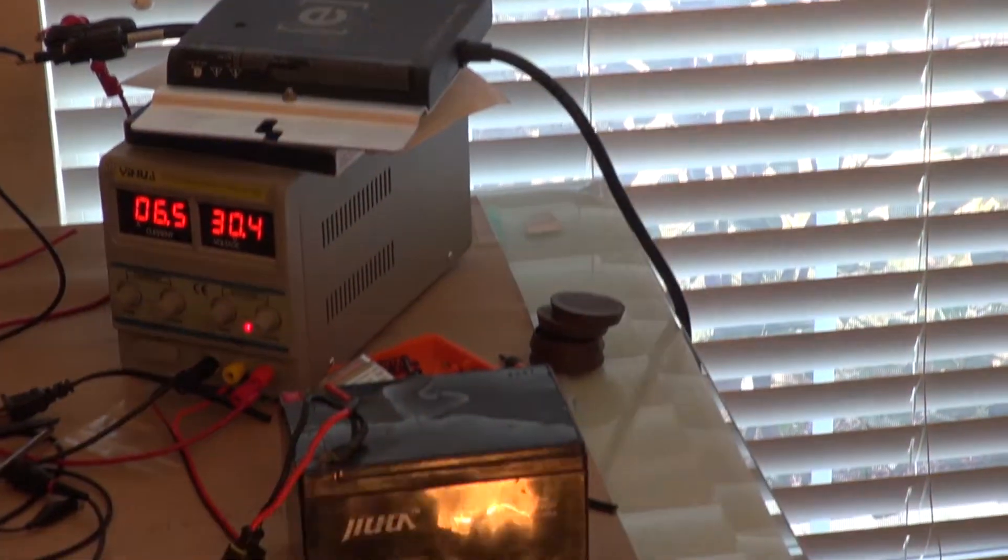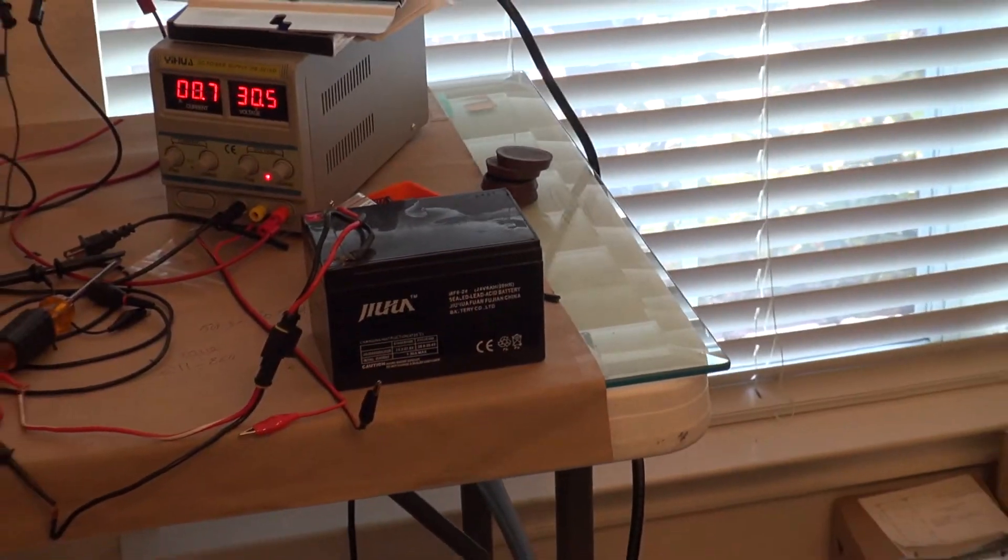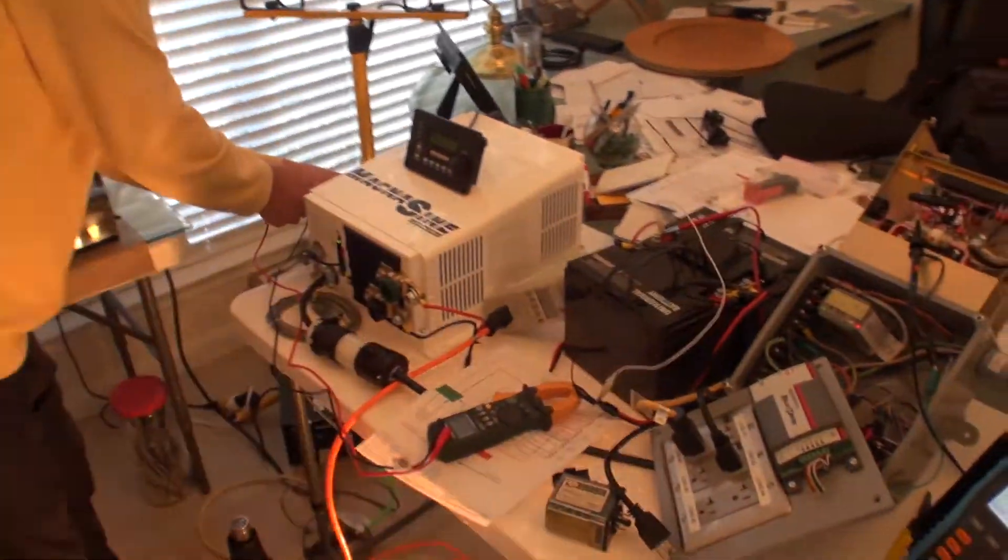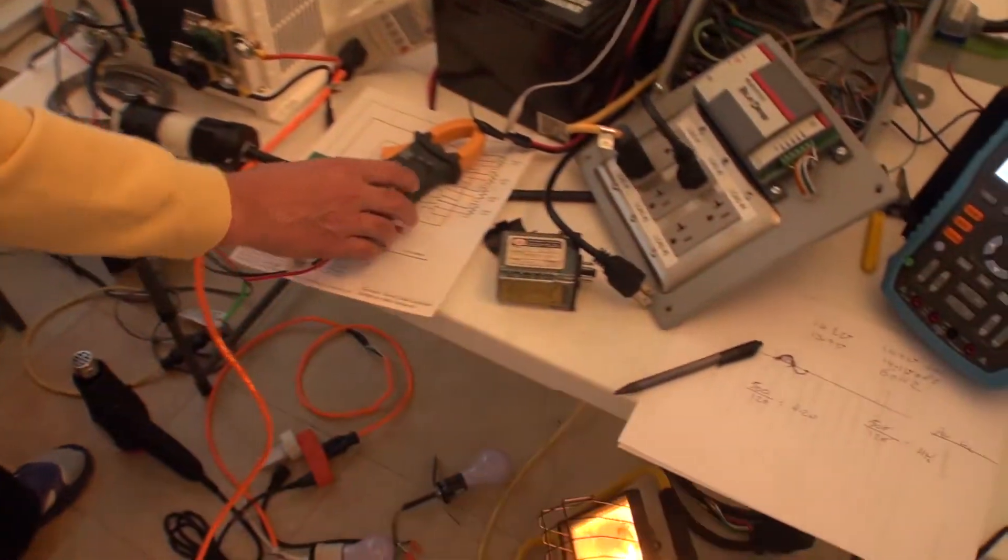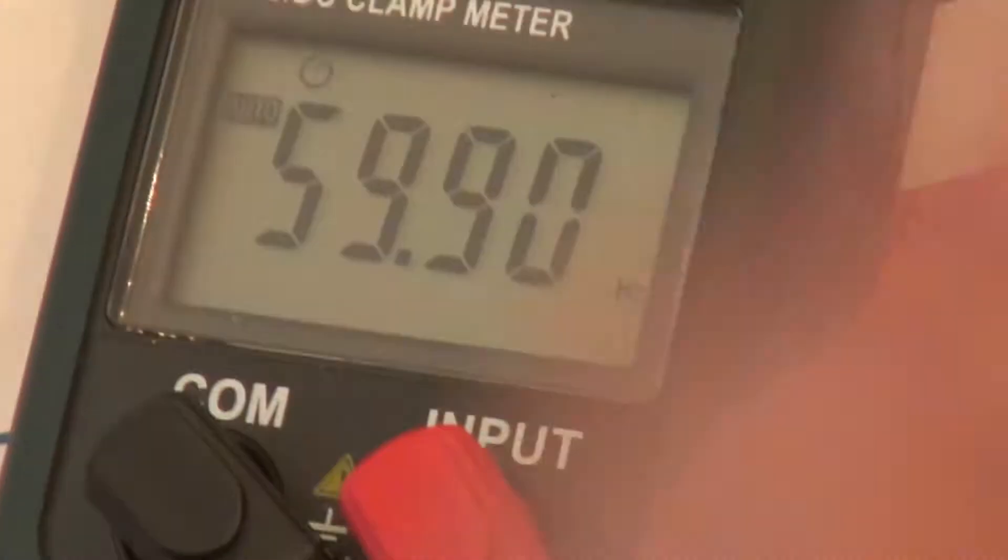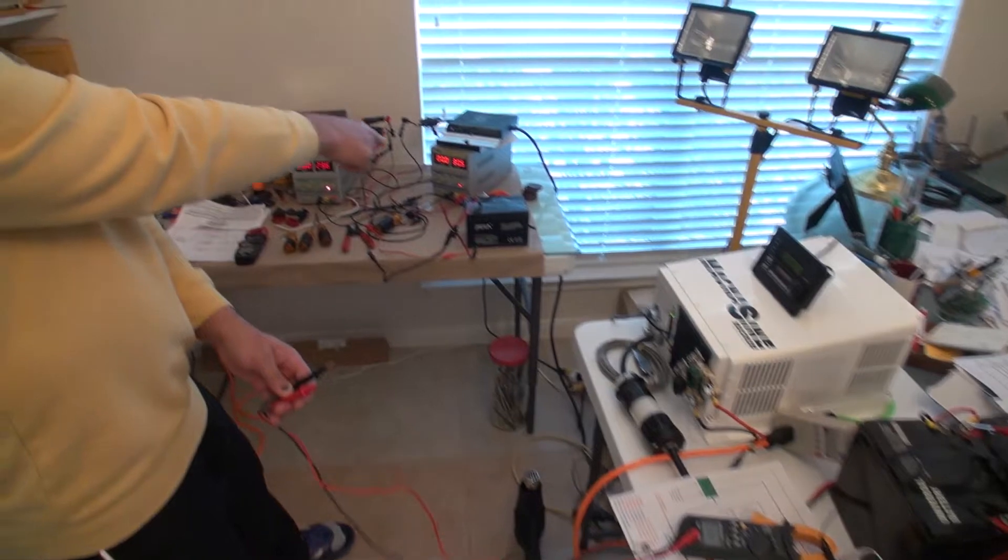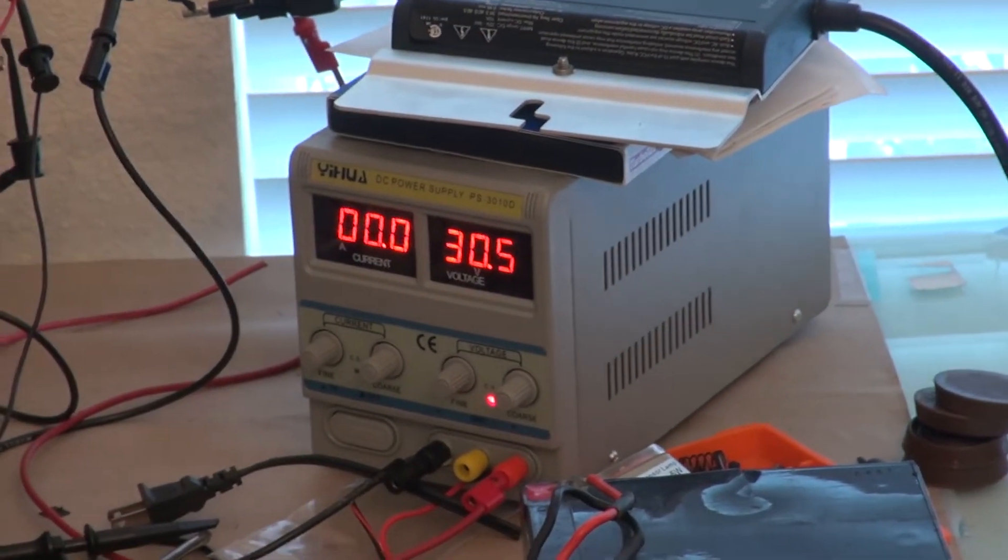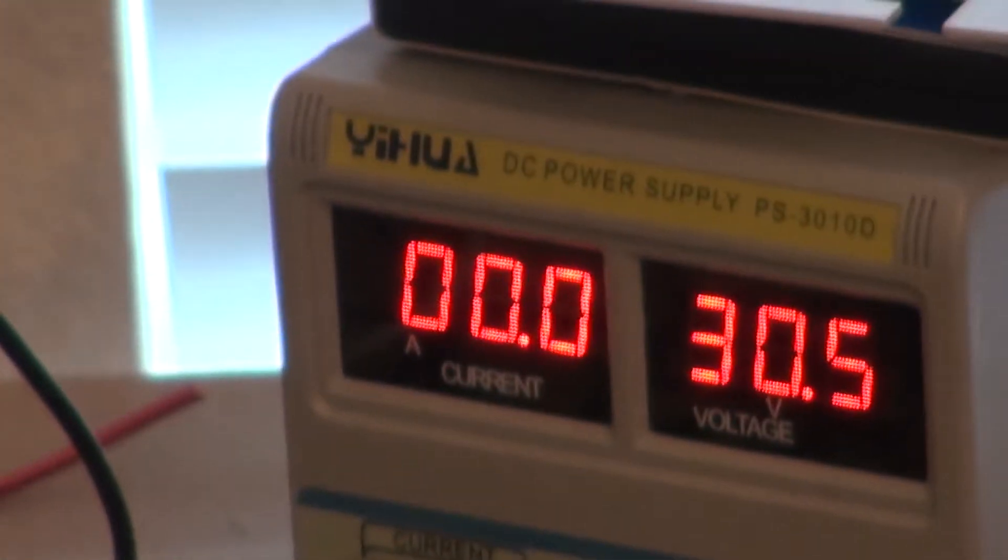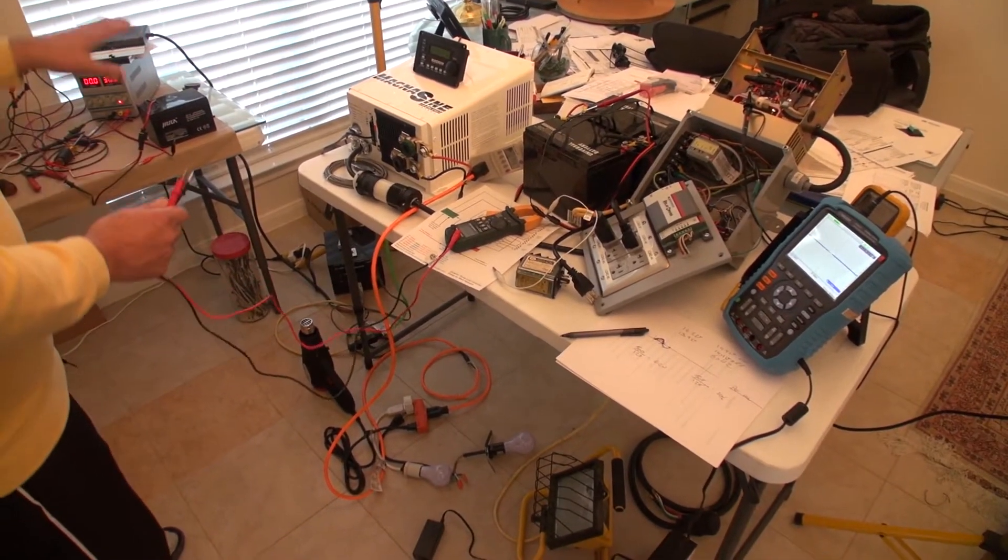We don't want to shut them off completely. Because when you shut them off completely due to the frequency change, they're going to stay off for five minutes. Let's take a look at the frequency right now. It's reading 59.9. I'm going to get rid of all my load by disconnecting this. Look at the frequency, 60.6. That is causing the micro inverter to go off. If you take a look at the micro inverter, they're both off. That is in case something happened to your dump load or you have a light bulb go out or the voltage raised too much, this inverter automatically shuts your micro inverter off.